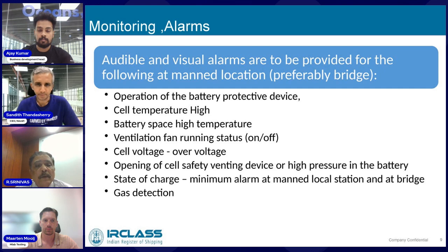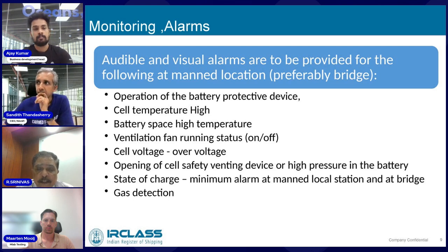Audible or visual alarms are required in case anything goes wrong. As Sandith said, there are various levels. What we are trying to monitor is the protective devices—whenever a protective device operates, it should be known and an alarm given: individual cell temperatures high, battery space temperature high, ventilation fan not running or AC system not running, cell voltage, and of course gas detection, which is very important and one of the first indications something is going wrong.